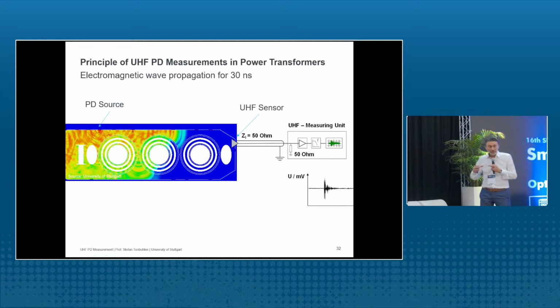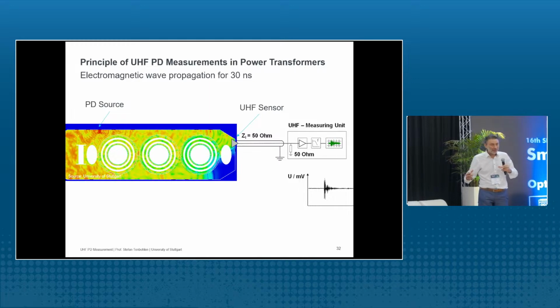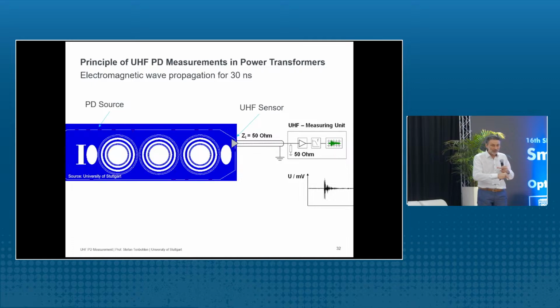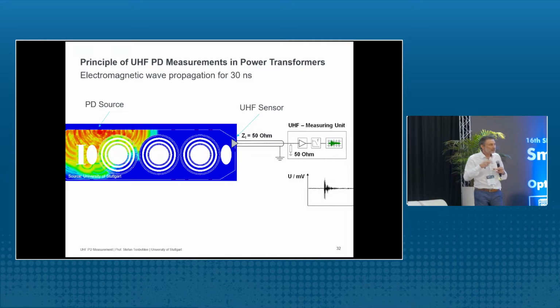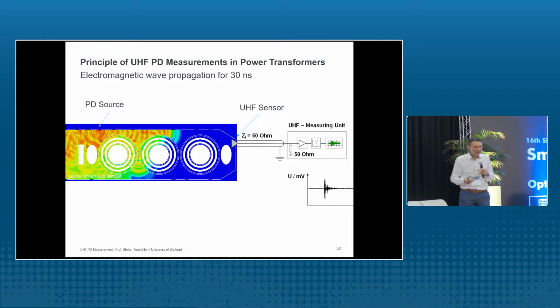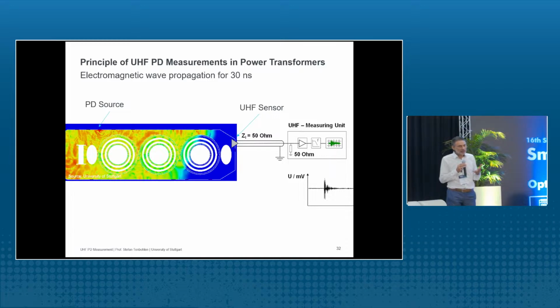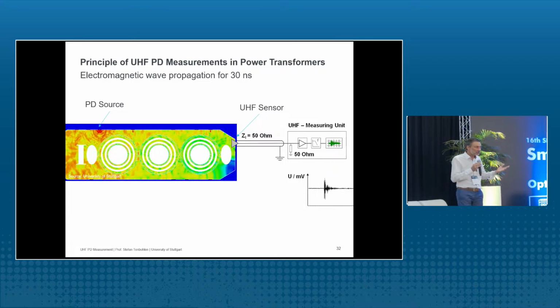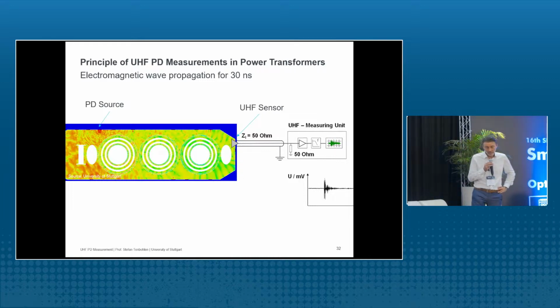And you can see here the transformer tank itself acts like a Faraday cage. So the electromagnetic waves cannot come out, but also electromagnetic waves from the outside cannot enter the transformer. So if you measure electromagnetic waves inside the tank, you can be sure that you have internal PD. So this technique is very immune to noise. During the factory acceptance test, you do a partial discharge measurement in the test field, but a test field is a very well-screened room, and there you do not have any noise. So for factory acceptance test, this technology is working pretty fine.